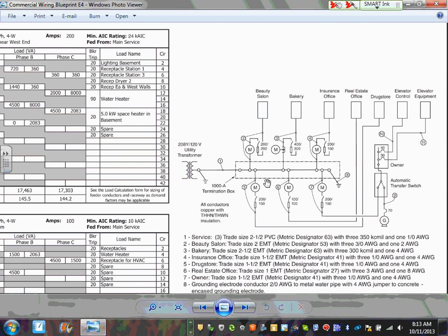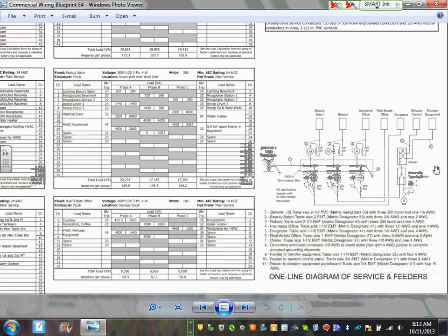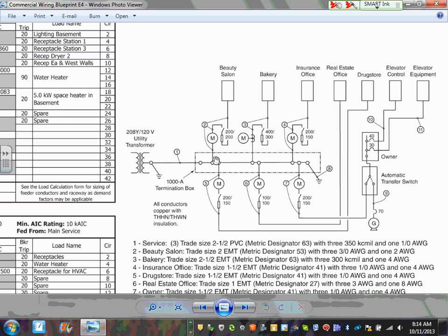Okay, here's the riser. Can you see the last thing, the riser or the one-line diagram? I want to emphasize this one a little bit. The way they did this project, they brought the power from Excel into a gutter, and they tapped from this gutter. They tapped it, 6 disconnects.